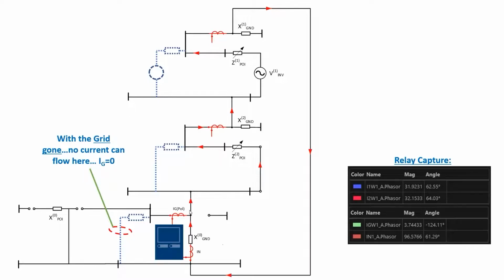Without digging too deep into the symmetrical components aspect of it, if you place the fault point inside of the transformer and you draw out the zero sequence portion of the circuit, what you'll find is IN is the only measurement, and that's exactly what we got. When fault current flows, it only flows through the IN portion of the transformer, and it doesn't go through IG. Basically the current's coming up through the neutral, it's just not leaving the transformer, it's contributing to its own fault. It's not actually leaving the IG node to go into the microgrid.